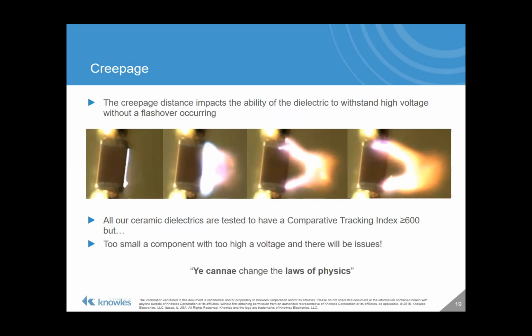Flashover, creepage distance. So we've got some slides there, which are very nice, taken at a very high-speed camera, showing how a flashover propagates. So you can see it starts on the surface, grows, then the inductance of the chip starts creating a magnetic field and blows the arc away from the surface. Happens in the blink of an eye. Ye cannae change the laws of physics. If you have a distance that the voltage can create a corona effect and start the arc happening, it will do so.